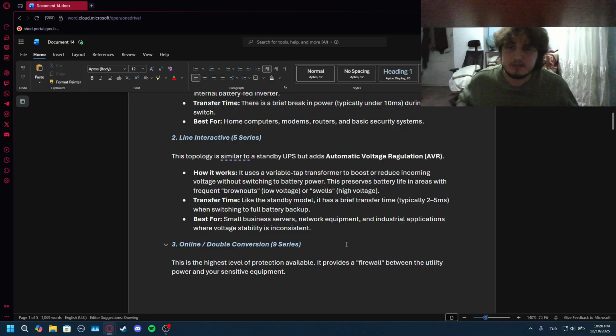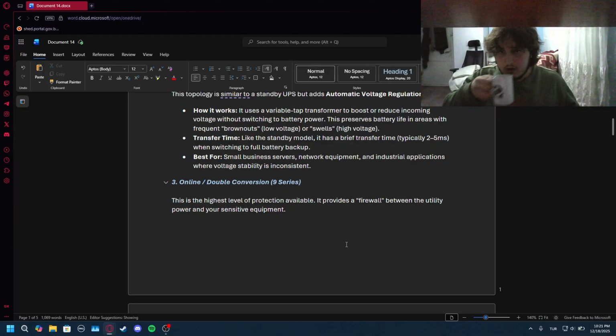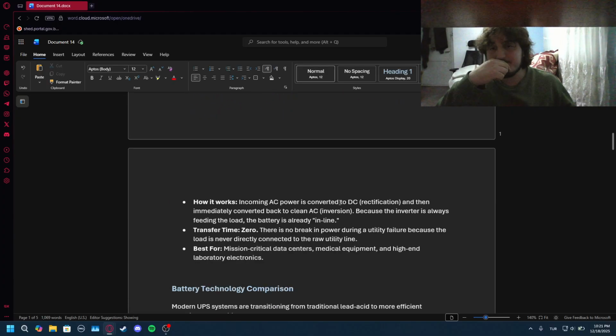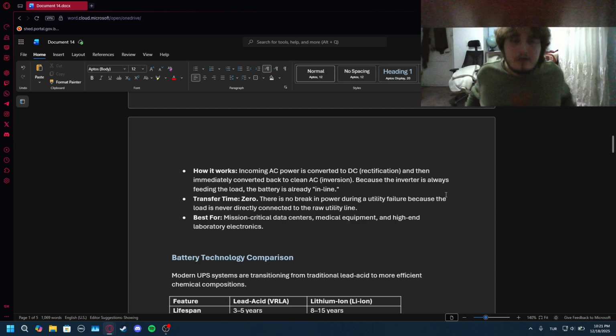Online double conversion 9 series. This is the highest level of protection available. It provides a firewall between utility power and your sensitive equipment. How it works: incoming AC power is converted to DC (rectification) and then immediately converted back to clean AC (inversion). Because the inverter is always feeding the load, the battery is already in line.